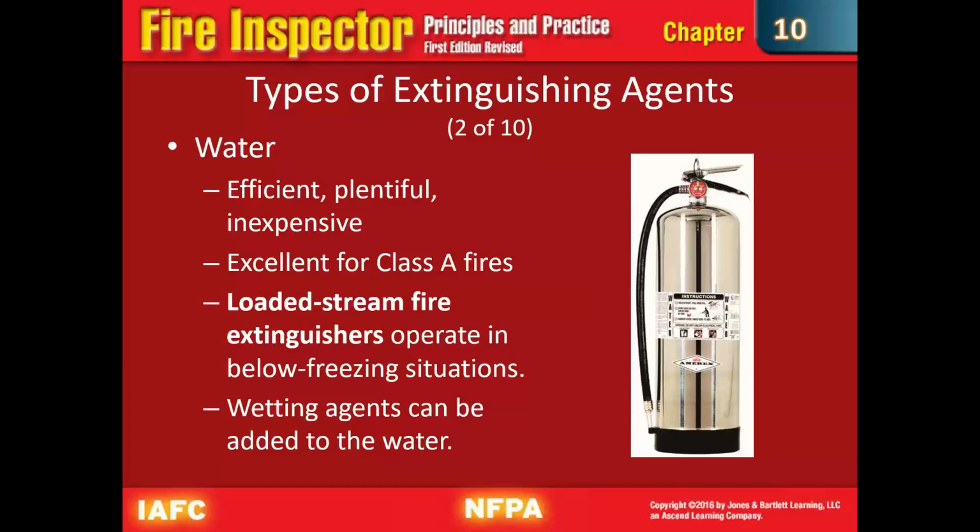I know we were running them where we'd have some Dawn dishwashing detergent just to act as a mild surfactant, which kind of helps put fires out. It has a little bit of a foaming action, and it's really good for Class A fires. It's pressurized with normal air. It's something that you can break down at the station, reload with water and detergent, recharge with an air line, and put back in service. The container needs to be checked every so often, pressure tested and all that.